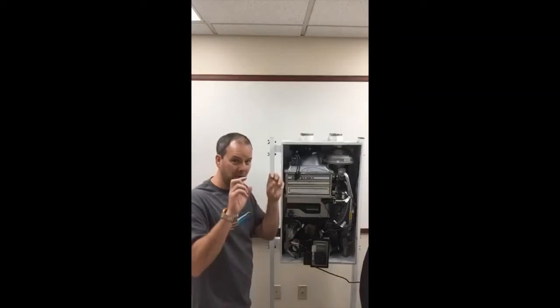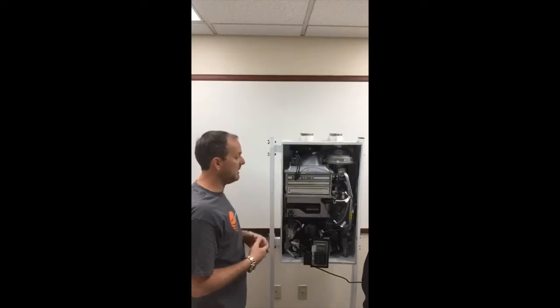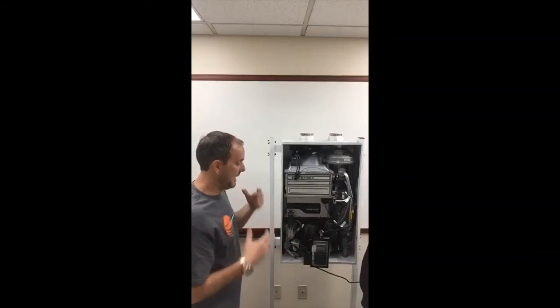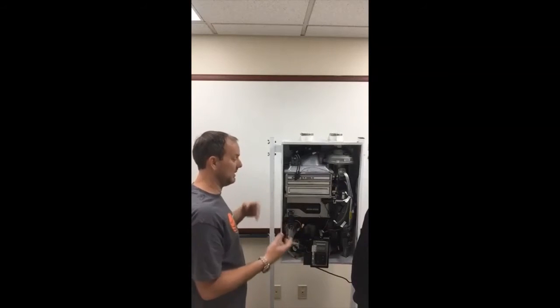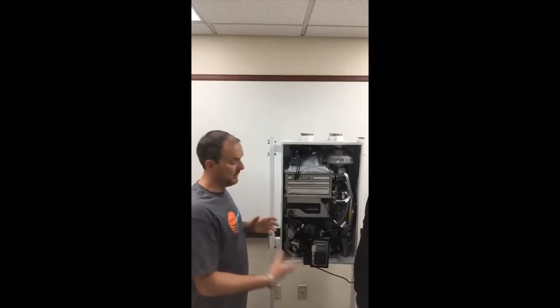Sometimes you'll save a few dollars and get a copper heat exchanger. Okay. Yeah. And we all understand copper. We have it in our homes typically for plumbing, but copper does wear out, and it does tend to not last as long as stainless steel. Right. So I like this particular unit. It does a great job exchanging the gas with our water temperature, so the heat exchanger does work correctly and very well. I don't feel it's necessary to use the copper for that because we get great performance out of this. The maintenance should be annual if you have no filter.